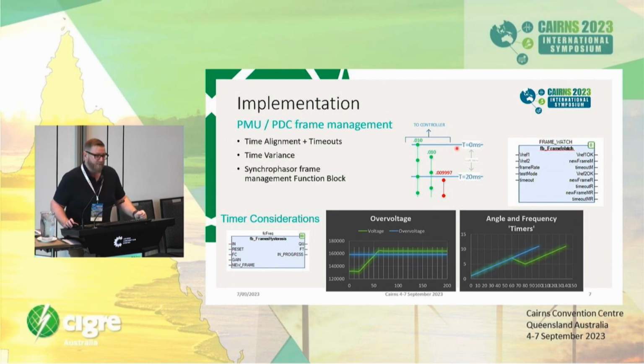I might need to step things up a bit. The next part is that when you're looking at synchrophasors, if you have an overvoltage element with a 60 millisecond pickup time, and you're typically using an automation timer of some kind internally at 60 milliseconds, and your samples are only 20 milliseconds apart, there's a good chance that if you miss a sample, that timer is still going to time out, but it's only ever seen 40 milliseconds of system data.